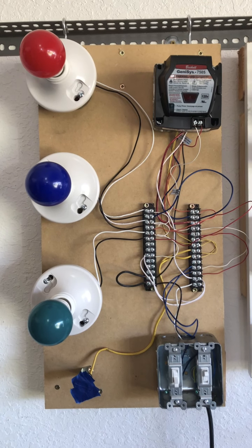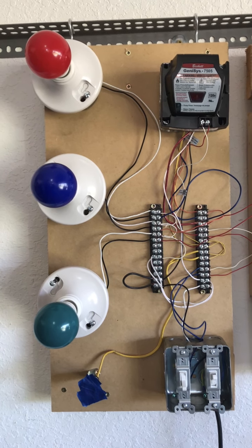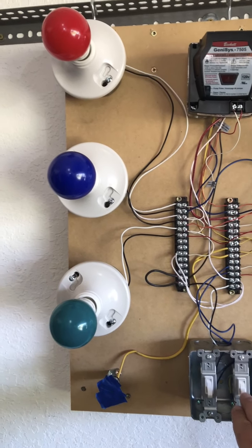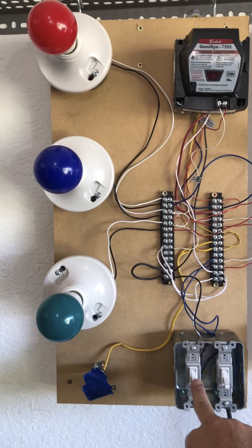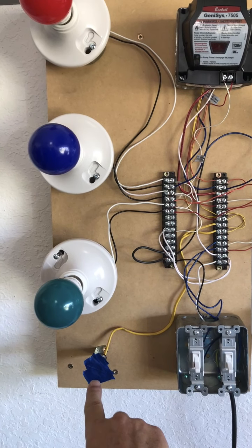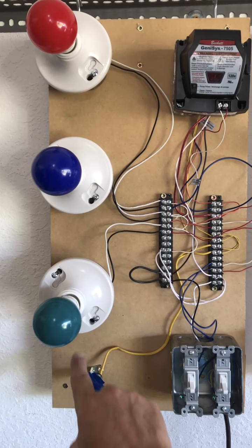Going to review the oil sequence of operation using a CAD cell primary on the trainer board here. Now we don't have a thermostat, so we have a power switch. We have our thermostat here, or switch for thermostat. Have my CAD cell eye down here. Right now it's covered so we don't see flame.